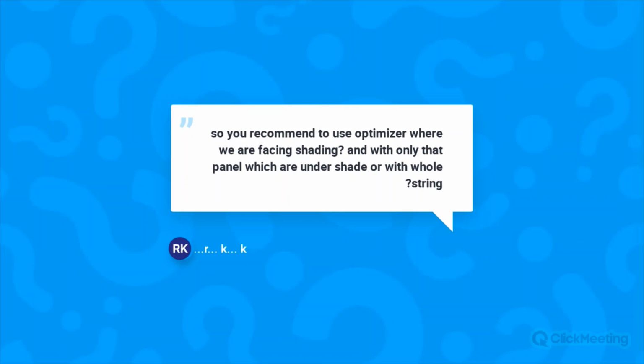So you recommend to use optimizer where we are facing shading and only that panel is under shade, or with the whole string? This is from Rafi Khan. So Rafi, if you followed closely, you would have noticed that we have already mentioned that full string optimization is not compulsory. The only thing that you have to watch out for is that you are meeting the minimum number of optimizers as stipulated by Huawei. For single phase systems between 2 to 6 kilowatts, the minimum number of optimizers that you need in a string is 4. So once you are meeting the 4 in a string, you are absolutely fine to go ahead. For 3-phase systems, the minimum is 6 optimizers in a string. So again, once you are meeting that criteria too, I believe you are absolutely fine to move ahead with the system. So any of this should work fine for you. You could do anywhere between the minimum and the maximum, if that is okay with your design.